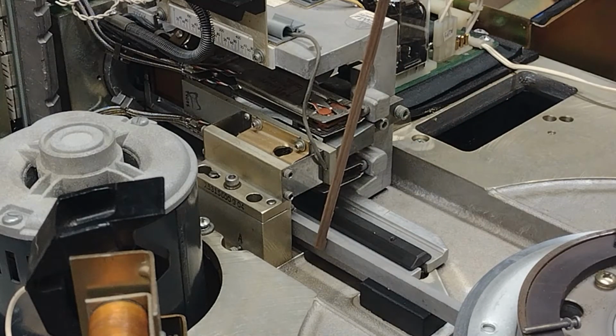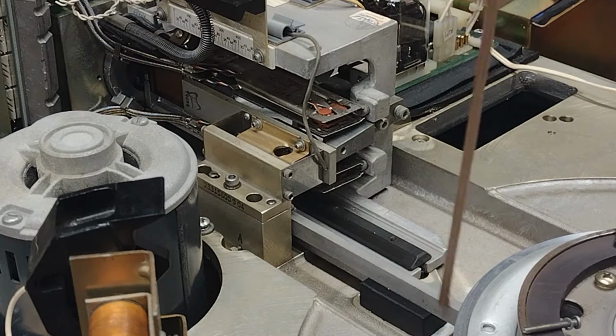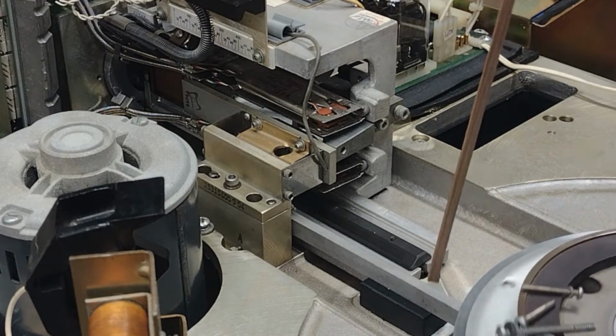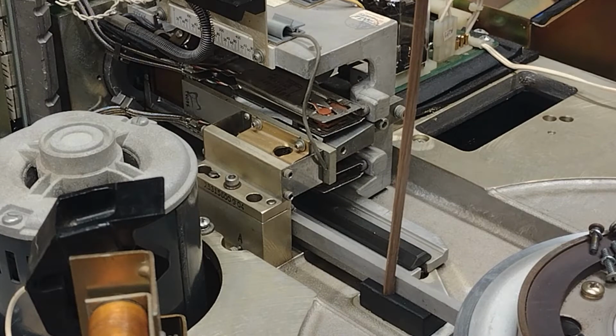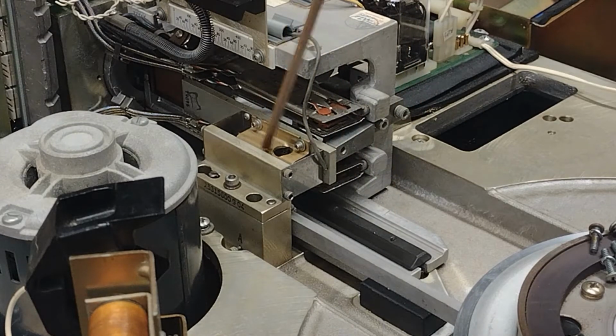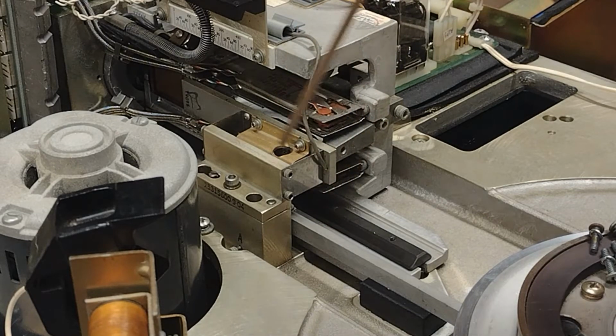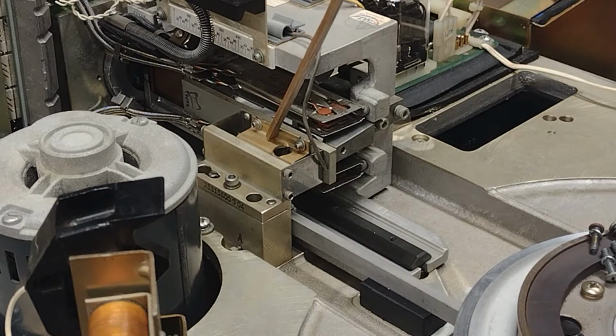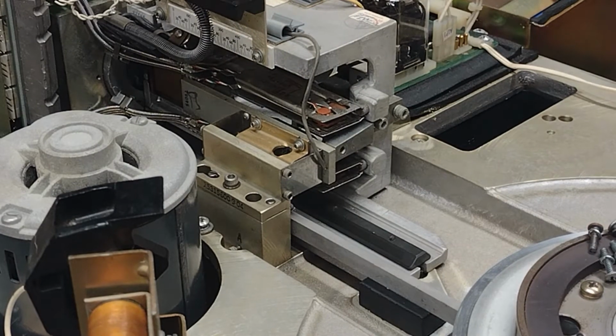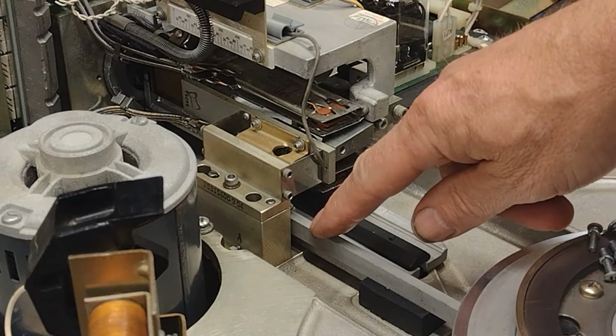Here we see an aluminum bar. This aluminum bar is attached to the frame down underneath the spindle here. It runs up, looks like it's got a little rubber cushion, and hooks into the position transducer that's fixed, the one that doesn't move. So that bar is attached to the position transducer, which does not move. The bar is made out of the same alloy of aluminum as the disc. Therefore, as the heat changes, if it gets warmer and colder, and that disc expands and contracts, this bar will do the exact same thing.